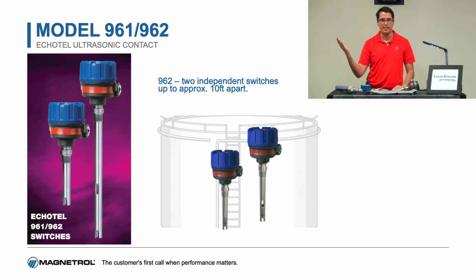And we have the 962, which is two independent switches. It's got two gaps on the rod, as you can see, obviously. One relay for the low level, one relay for the high level, or it can be a high, high, high, or a low and low, low. Or it can be a pump start, stop device as well. You do have to power this device. It is 24 volts DC. It can be 110 AC as well.